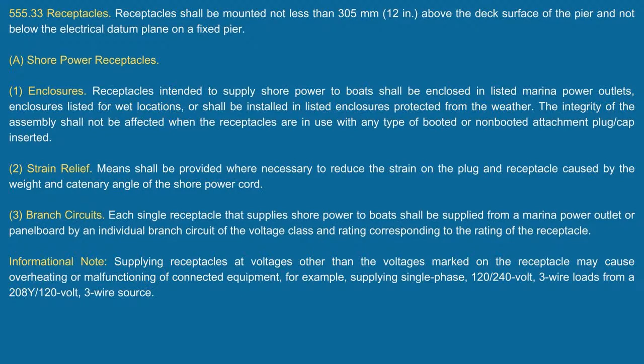And then if you look at the branch circuits in (3), what does it say? Each single receptacle that supplies shore power to boats shall be supplied from a marina power outlet or panelboard by an individual branch circuit of the voltage class and rating corresponding to the rating of the receptacle. Well, looky there. You just told me that when I go over there and I'm picking up my connection there to a receptacle, that's an outlet, and I've got to have GFCI protection. So is he going to say not only do I need GFPE, but I also need GFCI protection for the outlet that I'm plugging into for the shore power? Yeah. That, you see, is pretty much my argument.